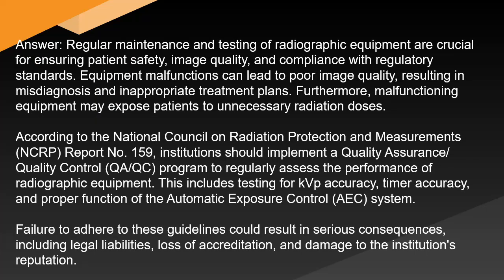Answer: Regular maintenance and testing of radiographic equipment are crucial for ensuring patient safety, image quality, and compliance with regulatory standards. Equipment malfunctions can lead to poor image quality, resulting in misdiagnosis and inappropriate treatment plans. Furthermore, malfunctioning equipment may expose patients to unnecessary radiation doses.